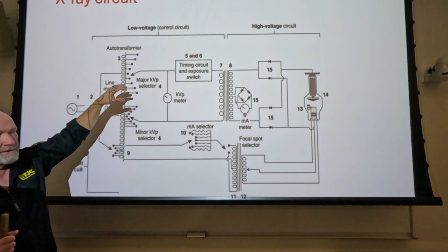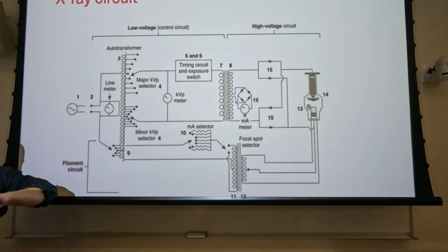What I didn't draw last semester is the difference between these two. Notice how these are more spread out, and we talked about that last week. So each one of these would incorporate more of the secondary side than what these down here do. So these are your major kVp adjustments and minor kVp adjustments. Again, you don't see that on your control panel unless you're working with a single phase machine. So major kVp is like 10 kVp, and then minor kVp is maybe 1 per click. So they've got great big knobs, and it goes clack, clack, clack every time you turn them. You turn the knob that says major kVp, and you're adjusted by about 10 kVp. So to dial it in, you have to use both.